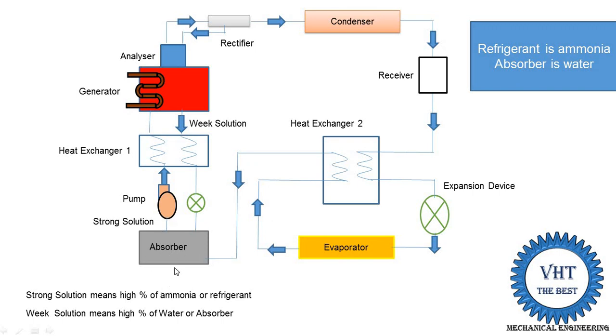In the absorber, water is available, so water and ammonia mix to create a strong solution. Strong solution means a high percentage of ammonia refrigerant; weak solution means a higher percentage of absorber (water). This strong solution is supplied into the generator by using a pump. In the pump, the pressure of the strong solution is increased up to 10 bar, then it goes through heat exchanger 1 into the generator. In the generator, heat energy is supplied using electric heaters, solar energy, waste gas, or waste steam from industries — any heat source can be used.